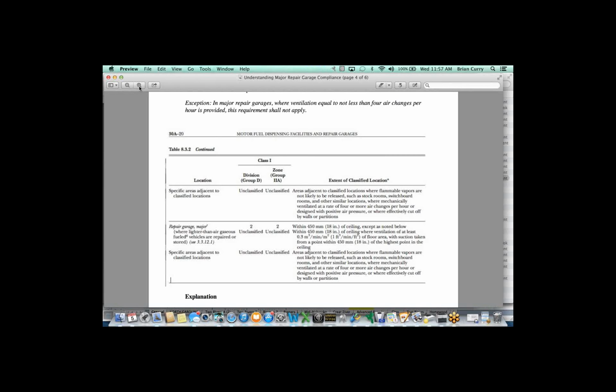Sound an alarm. We put an audible alarm on the outside of the building with a red strobe, so the fire department would obviously see that there was a problem, with a sign on the outside of the building that there was a methane condition. And not in every case, but depending on whether or not the shop had a fire alarm system, using the various outputs of the methane monitoring control system, we would tie that to a trouble signal on the alarm and have that programmed so you would be notified if it was after hours that there was a methane condition, as we call it, in the shop, and you knew at that point that the heaters were all turned off. Depending on how the site was set up, the overhead door was open, there was a security issue potentially, and then it would basically dictate a visit to the shop to see what was going on. So that's how we do it, and that's how I would do any other shop going forward.